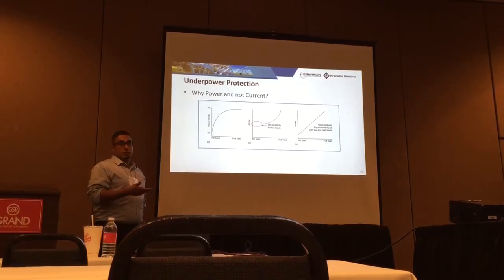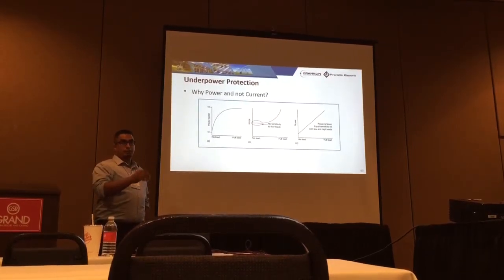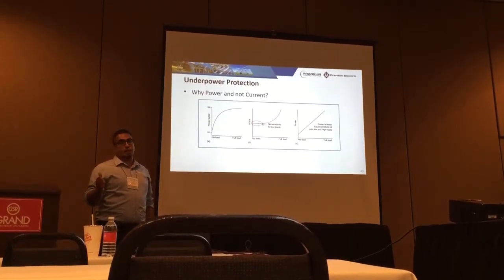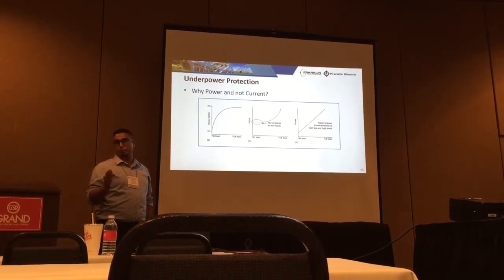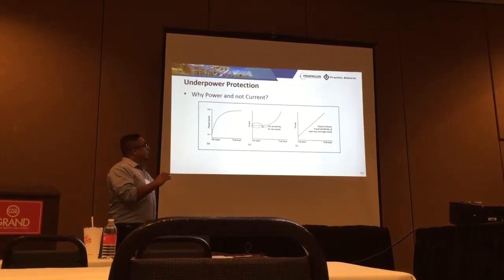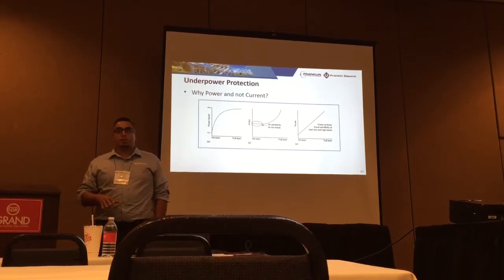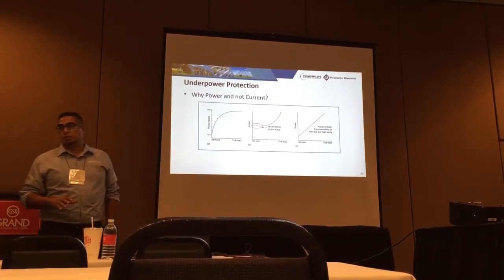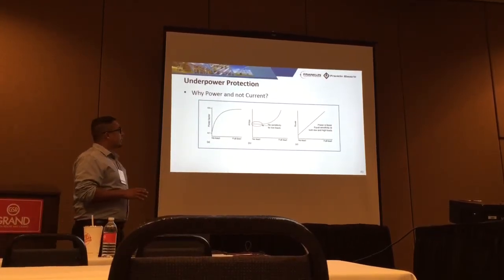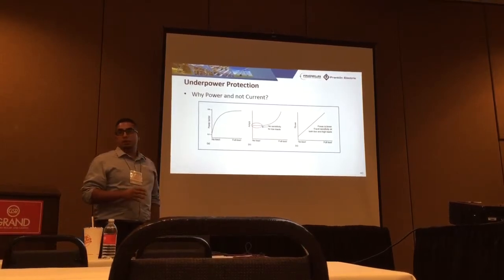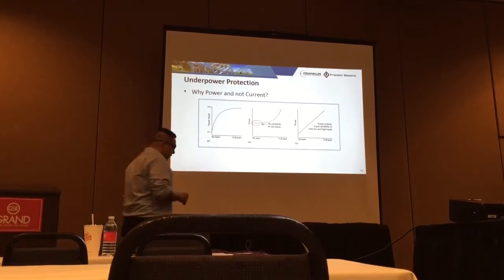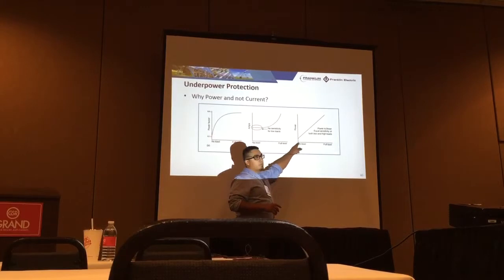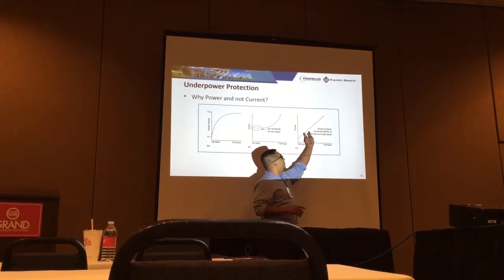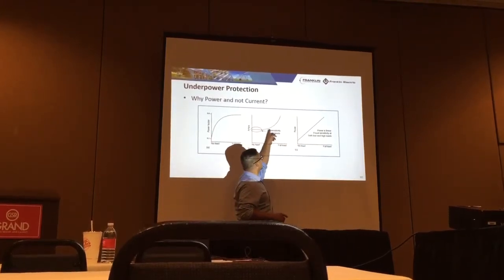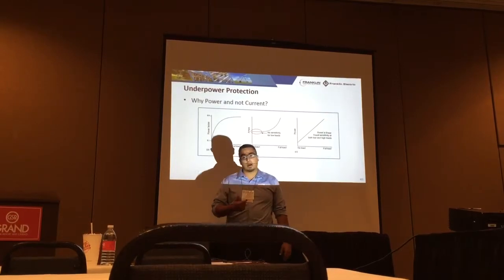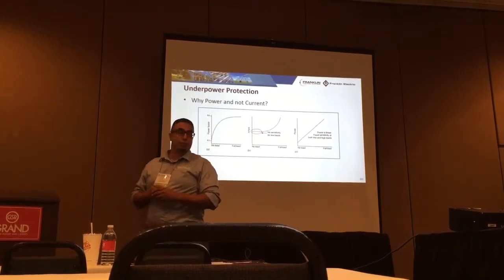So even the SSP panel, where we looked at 70-30, that's just a strict 70% of amps, trip. The new sub monitor and the IPS panels are looking at underpower. And underpower, when you look at it specifically in a pump system, offers a lot more adjustability in terms of when you're going to have a no-load condition, compared to a flattened out curve for amperage.